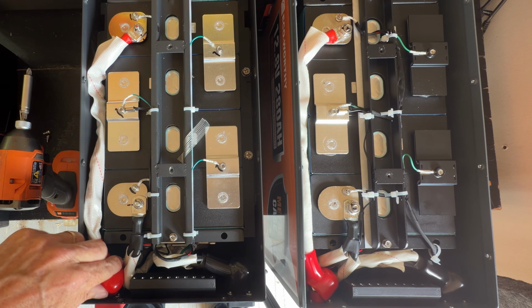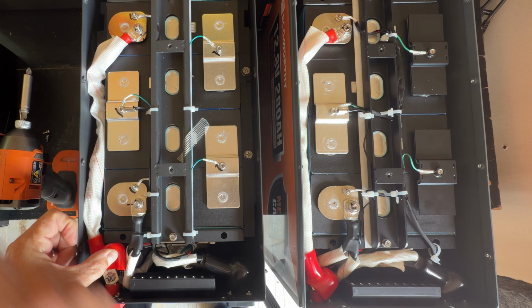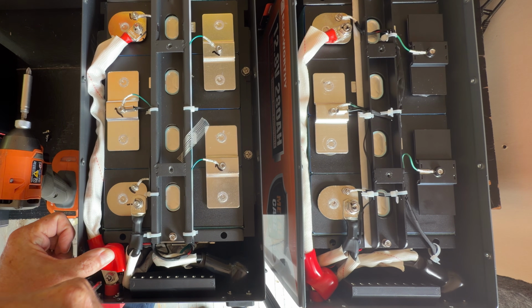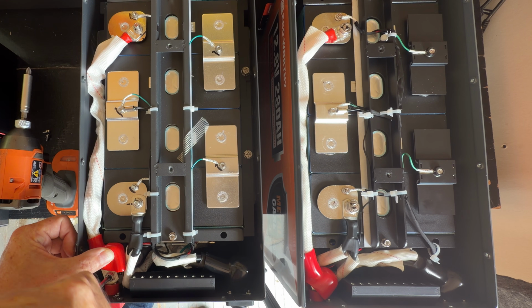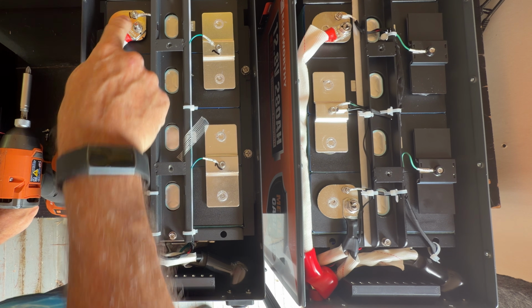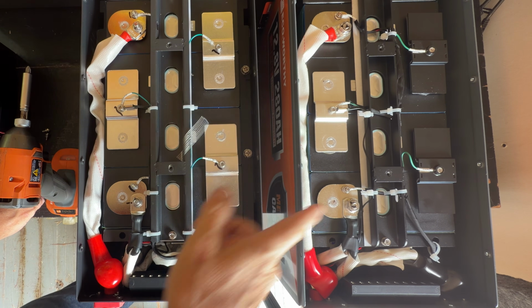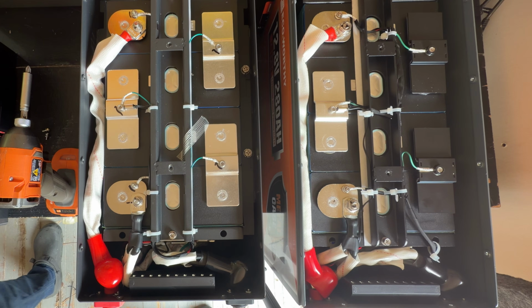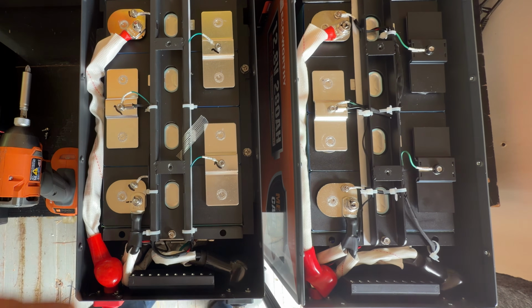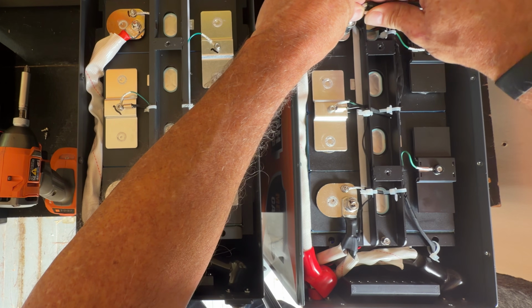So again, this is my highest rated battery that I've seen, and I'm going to check these screws here on the terminals - they're tight. Now I'm going to get a socket and check these. I did just notice the socket on these is a little bit bigger. These are standard size, and they are tight.